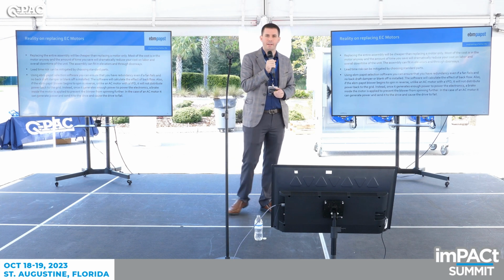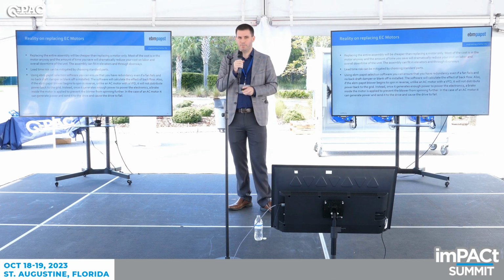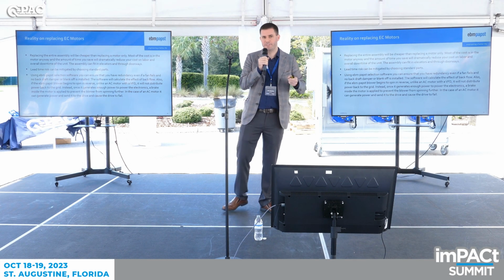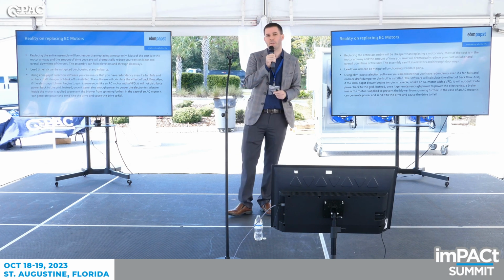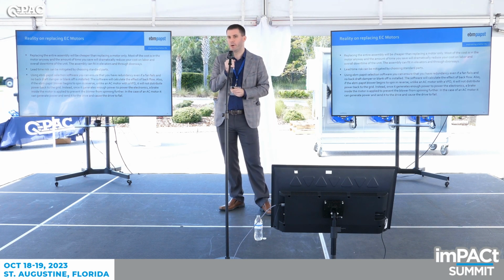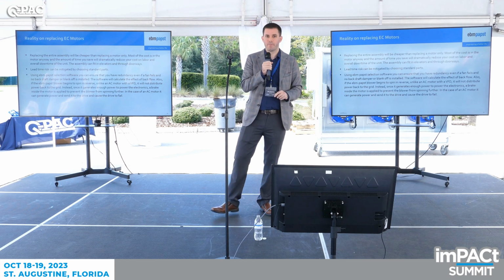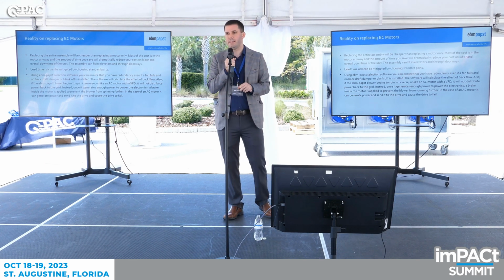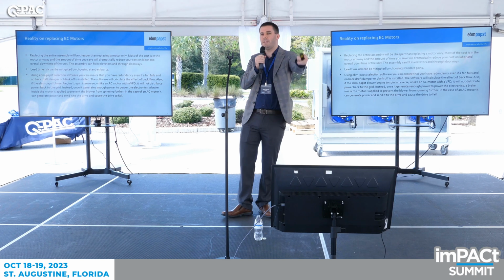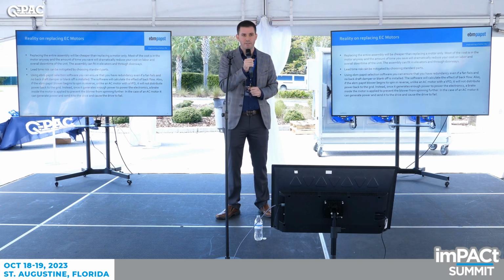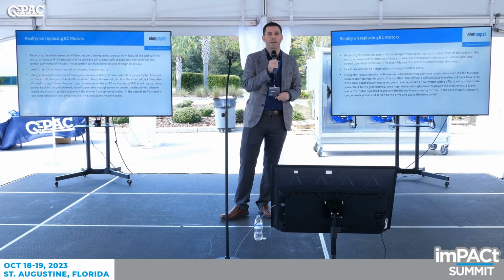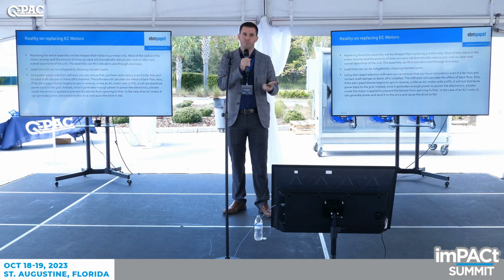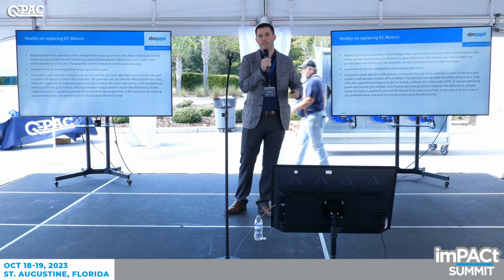Another thing is, I talked about the backdraft damper before. So if you have an array of fans and one of them fails, that fan is going to start spinning backwards. When you have an AC motor, that fan generates power, and if you have it hooked up to the same VFD as the other 3 fans, it's going to feed power back into that VFD and could damage the VFD. And you actually now have to replace a VFD, which is why lots of times you are including a backdraft damper to prevent that.